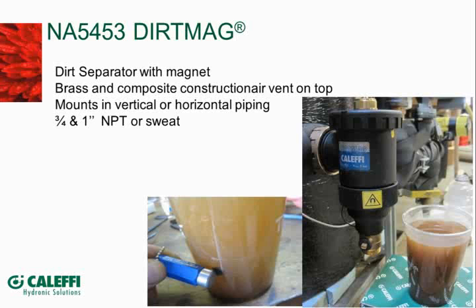Remember those slides showing ferrous particles that had adhered together and stuck to the inside of that rubber hose on the Geo systems? As long as that's moving around through the system, we can catch it with this device. In addition to a media that catches the big particles, scrubs them out, and lets them fall to the bottom of the cup where a valve can flush them out, it's got a magnetic band that catches those tiny particles — almost like shavings off a pencil with a pocket knife — that build up over years and eventually plug tubes, pumps, or zone valves. This device will get that.